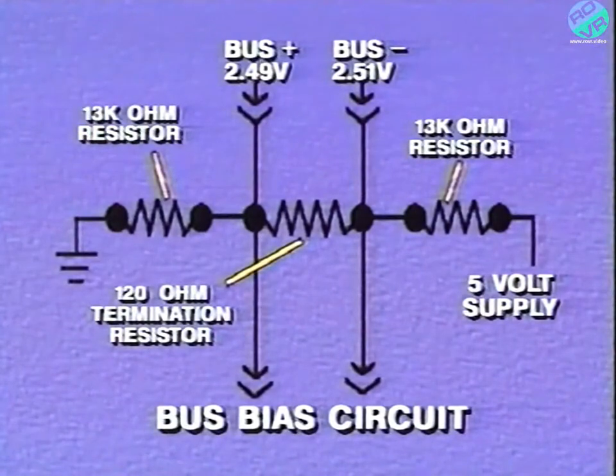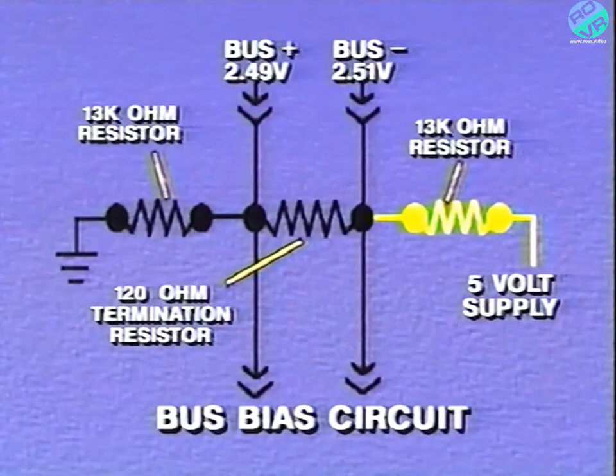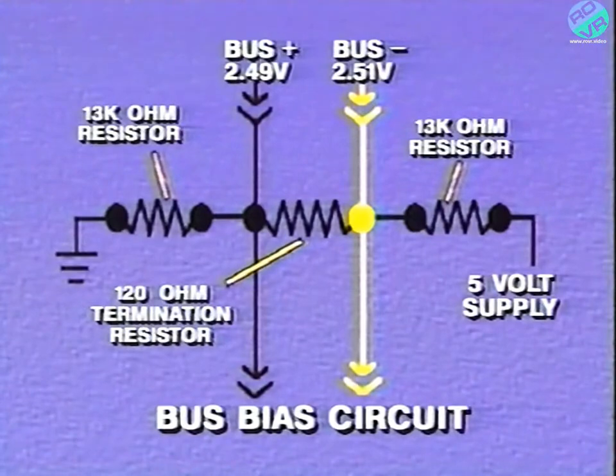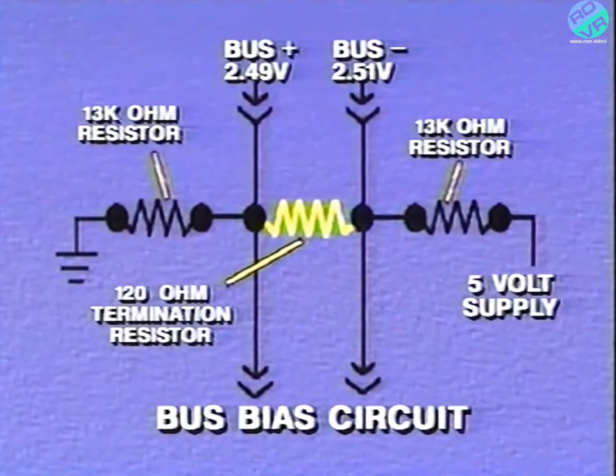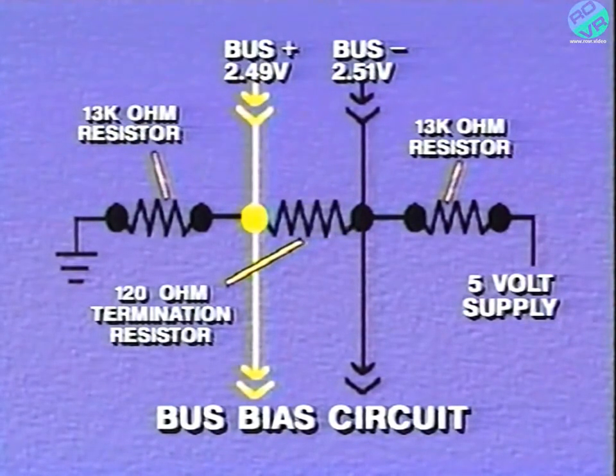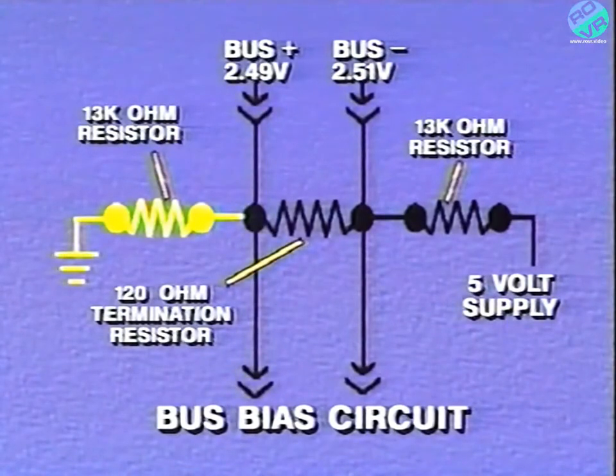The process of obtaining the bias voltage starts with a 5-volt supply going through a 13,000 ohm resistor, which drops the voltage to about 2.51 volts on bus minus. The current then flows through a 120 ohm termination resistor, causing a voltage drop of about 0.02 of a volt to bus plus. This termination resistor completes the circuit from bus minus to bus plus. The current then flows through another 13,000 ohm resistor to ground to complete the circuit.